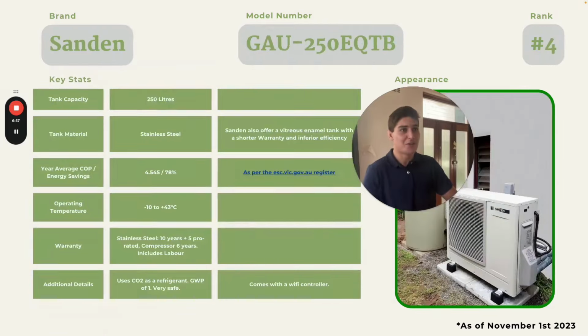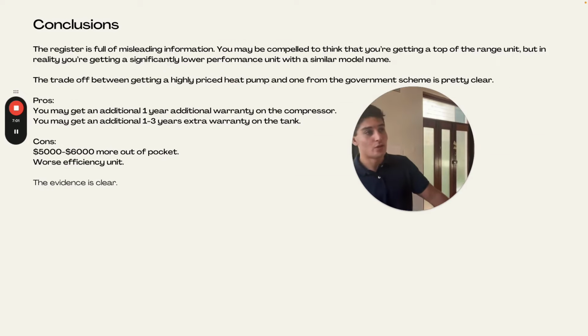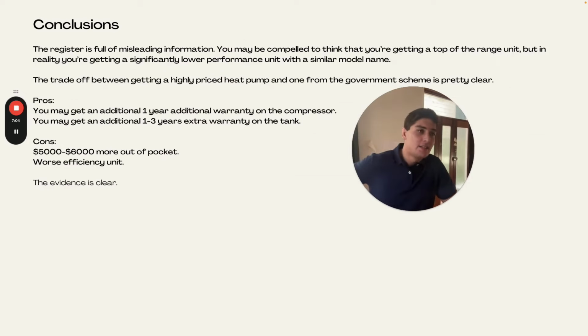I mean, I'll show you the conclusion now that I've drawn from this video. You probably would agree, but the pros of paying for a higher price system is you may get an additional 1 year warranty on the compressor. So some of them have 6 years, and you may get an additional 1 to 3 extra on the tank before it gets prorated. The cons are it's $5,000 to $6,000 more expensive and a worse efficiency unit.